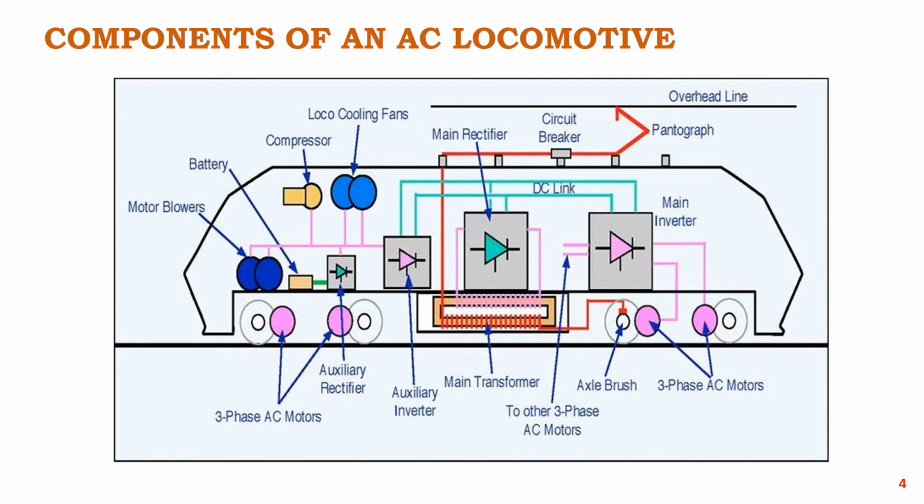Then train lighting or air conditioning system. Axle driven generators are used to charge batteries that power lights, fans and electrical fittings. For powering air conditioner equipment, an inverter is used to convert the DC output of a set of batteries to 415 volt AC. Older coaches use a bank of 24-volt batteries, while 110 volt is used in newer coaches. In many air conditioner coaches, a mid-on generator is used.